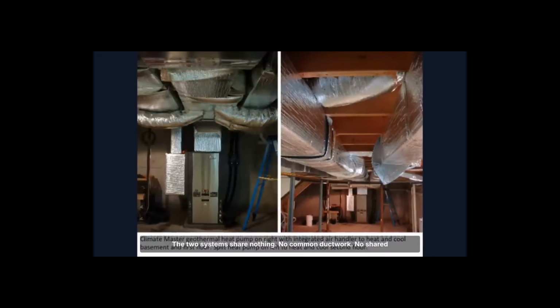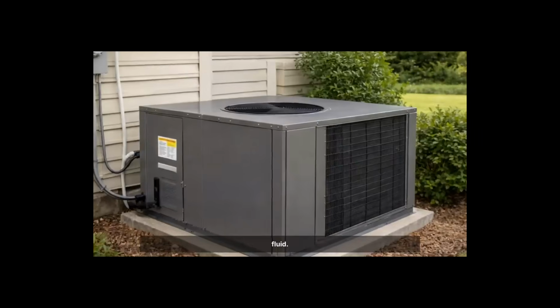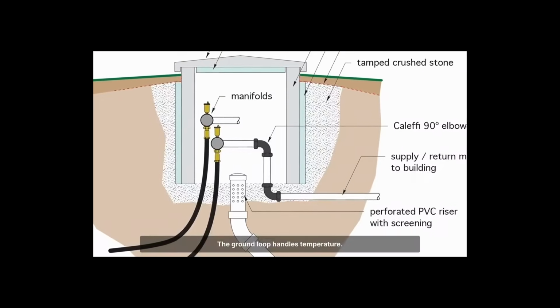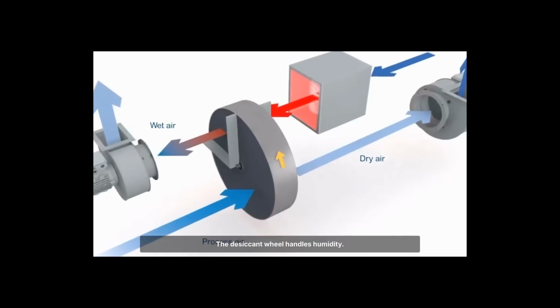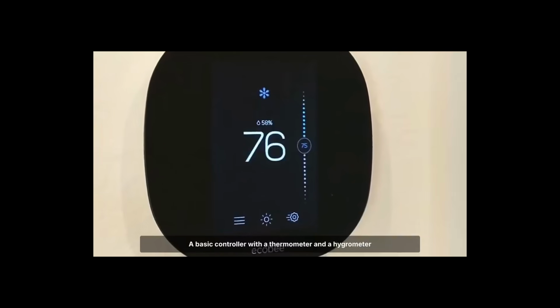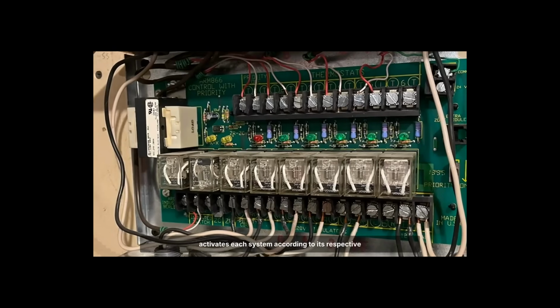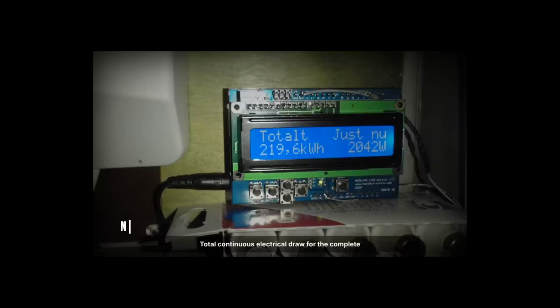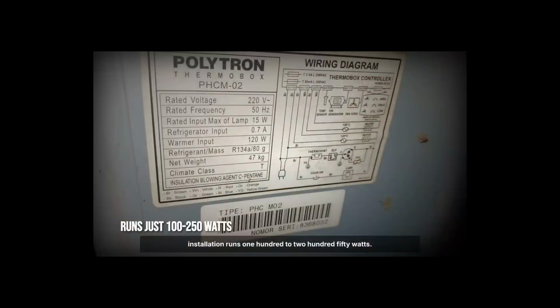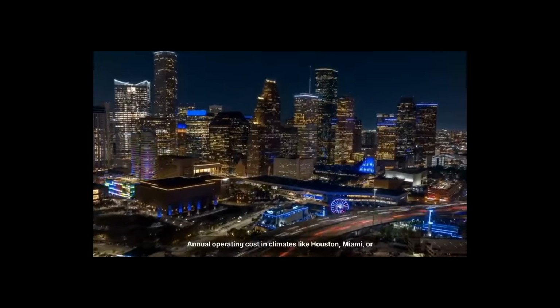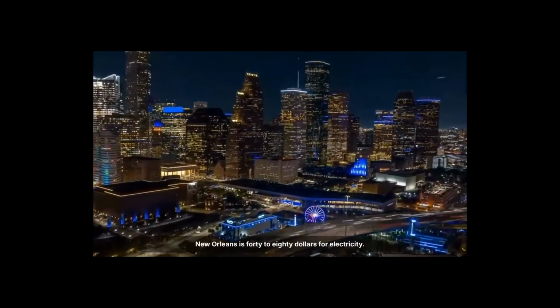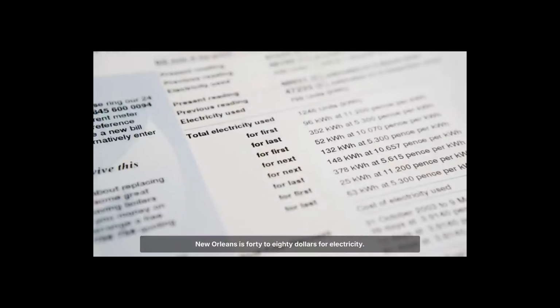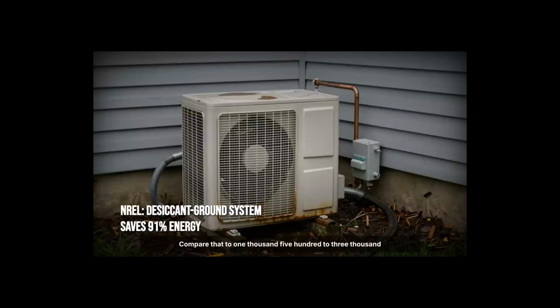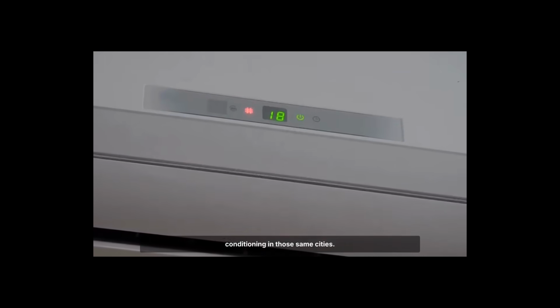The two systems share nothing. No common ductwork, no shared fluid. They operate independently. The ground loop handles temperature. The desiccant wheel handles humidity. A basic controller with a thermometer and a hygrometer activates each system according to its respective measurement. Total continuous electrical draw for the complete installation runs 100 to 250 watts. Annual operating cost in climates like Houston, Miami, or New Orleans is $40 to $80 for electricity. Compare that to $1,500 to $3,600 per year running conventional air conditioning in those same cities.